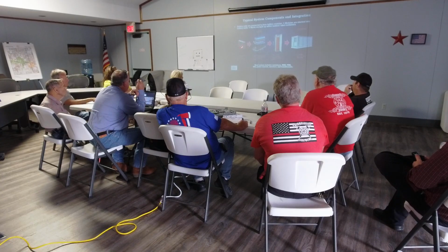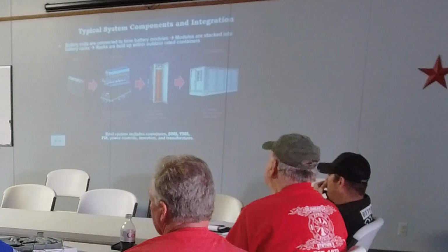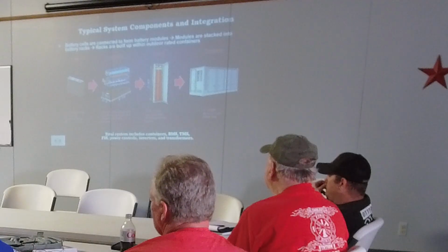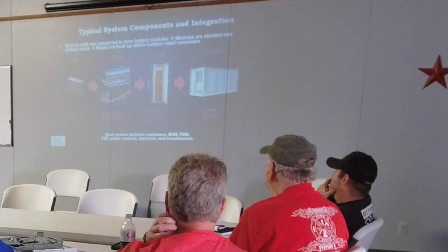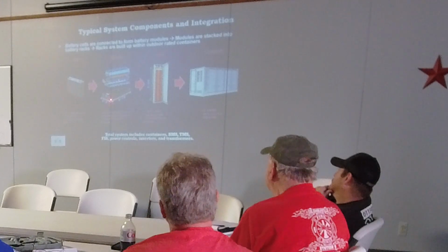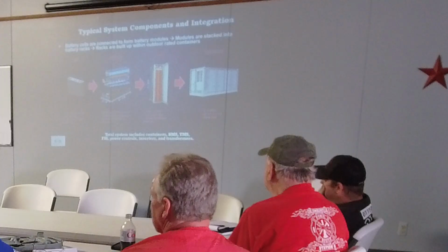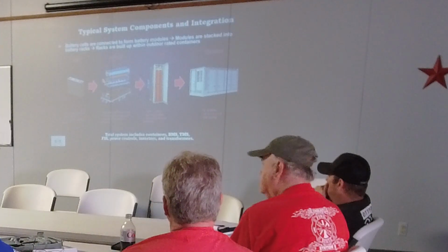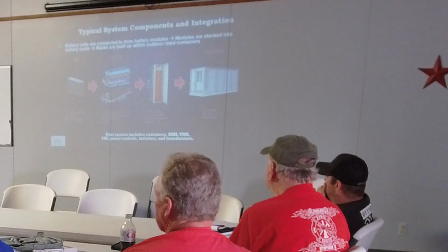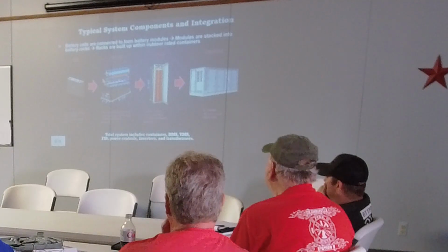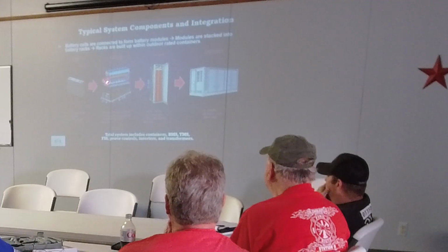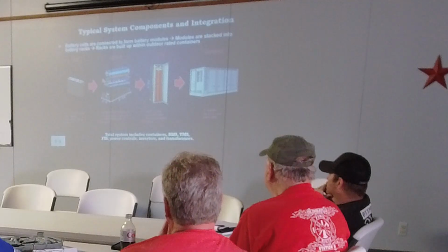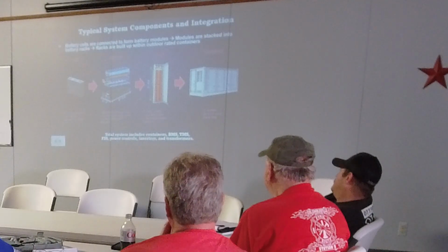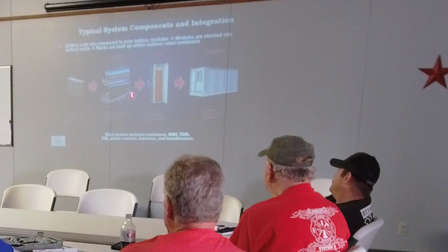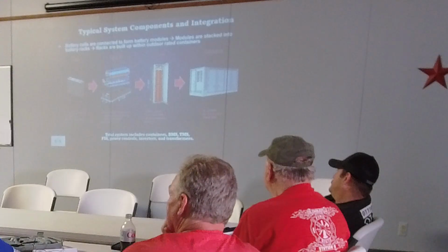Let's take a dive inside. Over here on the far left is a battery cell, a typical cell. Think about the largest textbook you ever had in school. That's it. It's heavy. This is where the weight comes from. They're about 3.7 volts nominally DC. They'll take a number of those cells and assemble them into this module. The module has a cooling plate, which can either heat or cool, depending on what's required. It'll have sensors for voltage, temperature, states of charge, rates of discharge. Then it'll have what's called an aerogel lining, and that's for thermal insulation, to prevent heat from propagating outward if an event happens. And then it's sealed up, and it has a vent on the side so that it doesn't build up pressure.